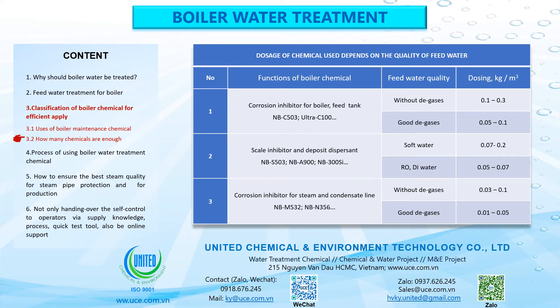2. Function: Scale inhibitor and deposit dispersant — NBS 503, NBA 900, NB-300Si. Soft water: dosing 0.07 to 0.2 kg/m³. RO or D-mixed bed water: dosing 0.05 to 0.07 kg/m³. 3. Function: Corrosion inhibitor for steam and condensate line — NBM 532, NBN 356. Feed water without degassing: dosing 0.03 to 0.1 kg/m³. Feed water with good degassing: dosing 0.01 to 0.05 kg/m³.